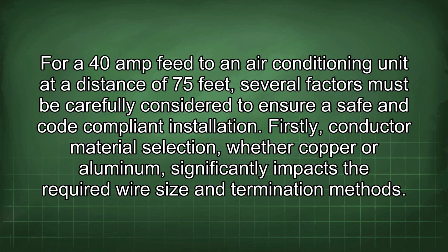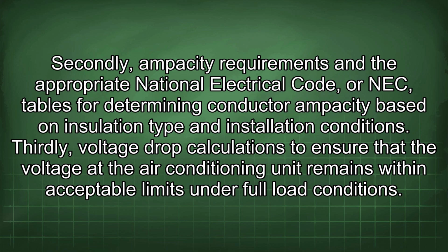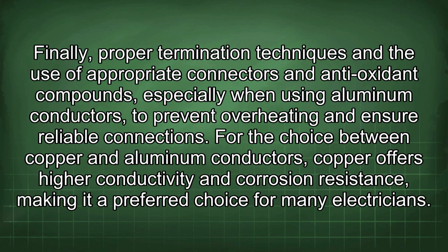For a 40 amp feed to an air conditioning unit at a distance of 75 feet, several factors must be carefully considered to ensure a safe and code-compliant installation. Firstly, conductor material selection, whether copper or aluminum, significantly impacts the required wire size and termination methods. Secondly, ampacity requirements and the appropriate National Electrical Code, or NEC, tables for determining conductor ampacity based on insulation type and installation conditions. Thirdly, voltage drop calculations to ensure that the voltage at the air conditioning unit remains within acceptable limits under full load conditions. Finally, proper termination techniques and the use of appropriate connectors and antioxidant compounds, especially when using aluminum conductors, to prevent overheating and ensure reliable connections.